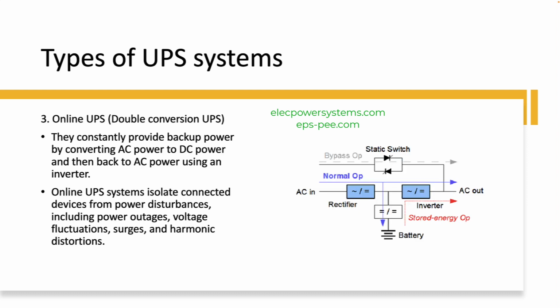Online UPS. Double conversion UPS. Online UPS systems provide the highest level of power protection. They constantly provide backup power by converting AC power to DC power and then back to AC power using an inverter. Online UPS systems isolate connected devices from power disturbances, including power outages, voltage fluctuations, surges, and harmonic distortions. They offer seamless power transitions and deliver continuous, clean power, making them ideal for sensitive equipment, data centers, medical facilities, and industrial applications.